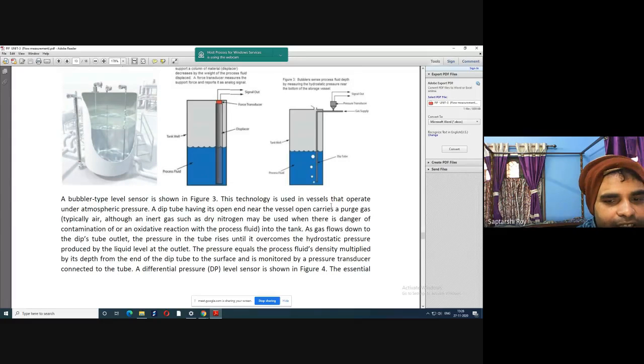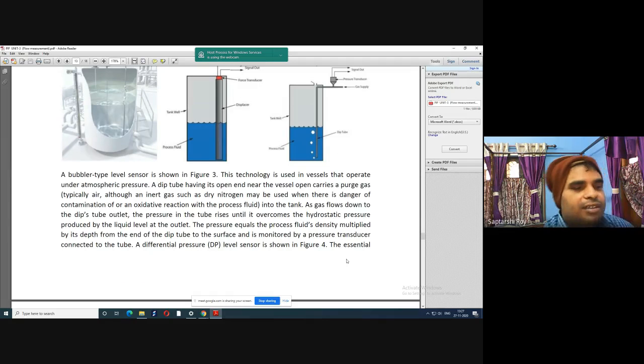এখানে কি হচ্ছে, this technology is used in vessels that operate under atmospheric pressure. A dip tube having its open end near the vessel bottom carries a purge gas, typically air, although an inert gas such as dry nitrogen may be used. When there is danger of contamination or an oxidation reaction with the process fluid in the tank, a gas flows down to the dip tube outlet. The pressure in the tube rises until it overcomes the hydrostatic pressure produced by the liquid level at the outlet. The pressure equals the process fluid density multiplied by the depth from the end of the dip tube to the surface and is monitored by a pressure transducer connected to the tube.